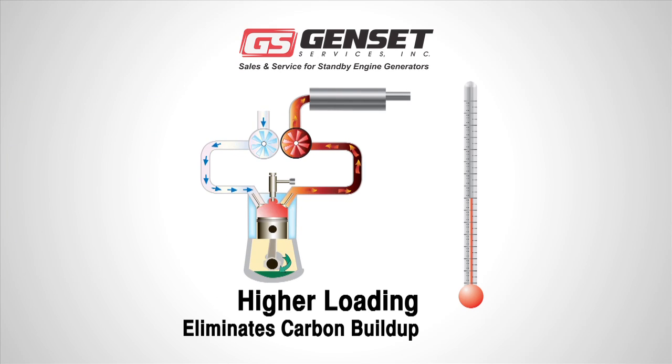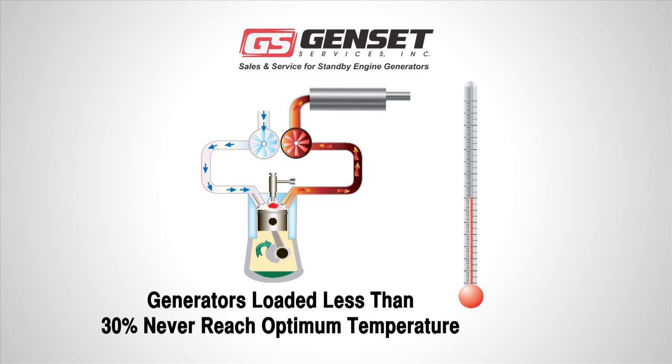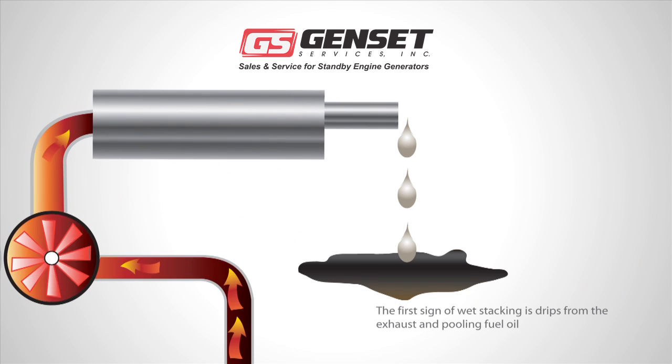and burns off unused fuel and carbon deposits in the exhaust system, a condition known as wet stacking. Wet stacking is a condition where unburnt fuel and carbon deposits build up in the exhaust system, producing smoke and unnecessary pollution. Generator systems loaded less than 30% never reach their optimum operating temperature. A generator that is continually run on a light load will start to exhibit the symptoms of wet stacking.